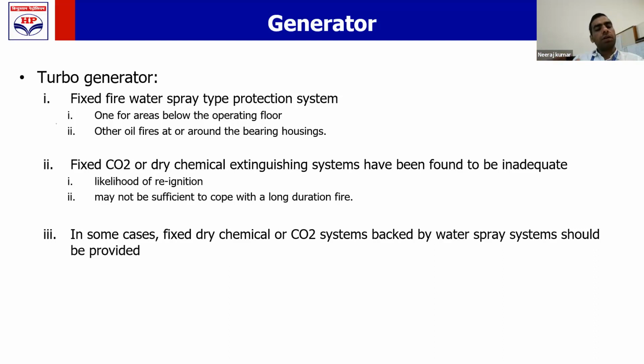In that, the fixed fire water spray system shall be at 2 levels. One for the area below the operating floor. Generally, a gas turbine will have an operating floor, above which the turbine and generator are installed. Below that will be a below-operating area in which the lube oil tank and many other things will be there. So one fixed fire water spray system for the below-operating area and another for firefighting around the bearing housing. Leak of lube oil from the bearing housing is not uncommon, and for that, a fire water spray system is required by this standard.